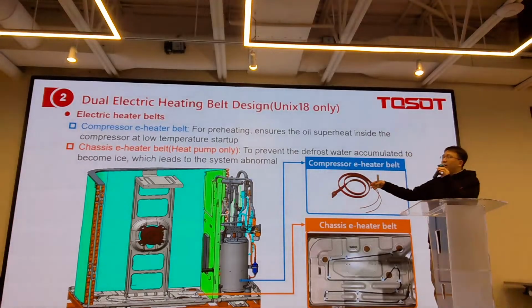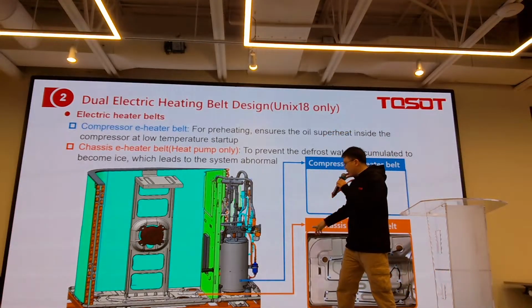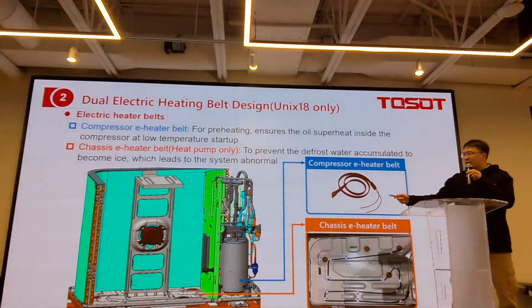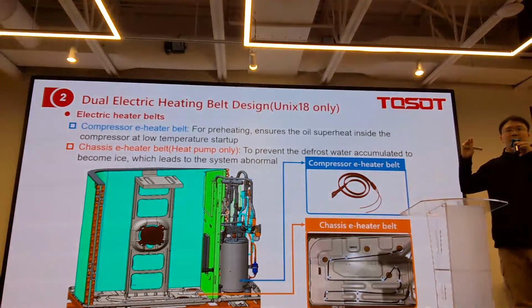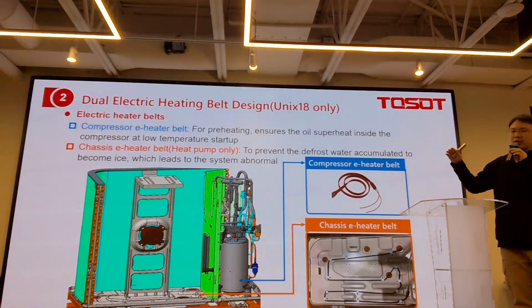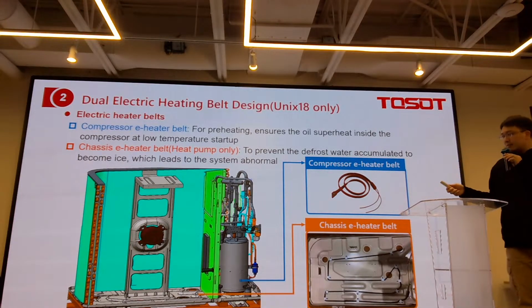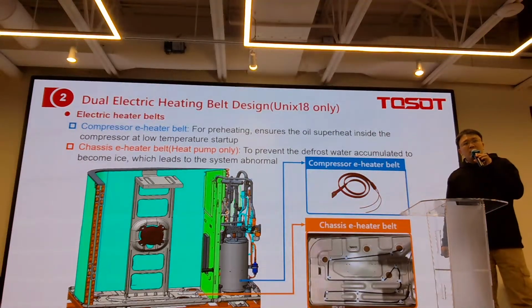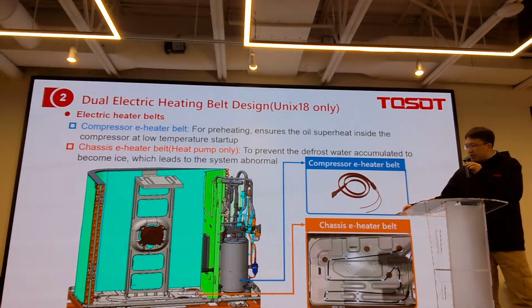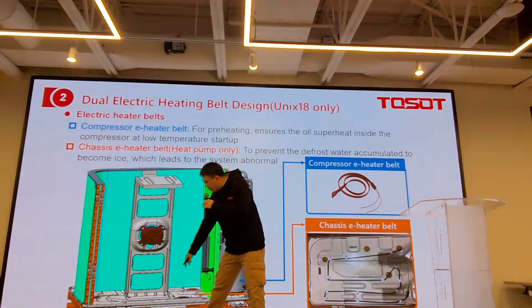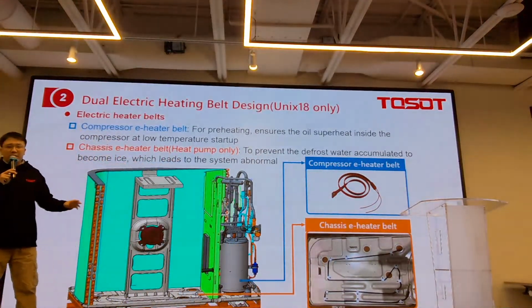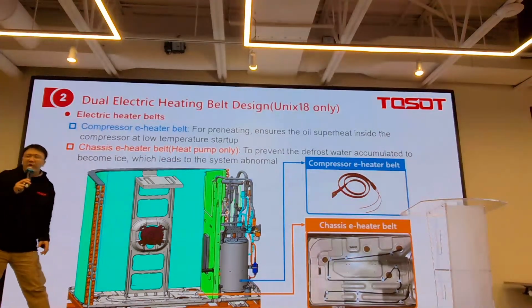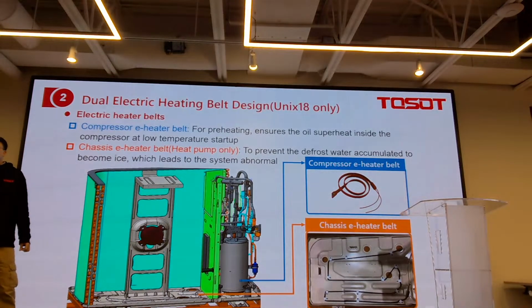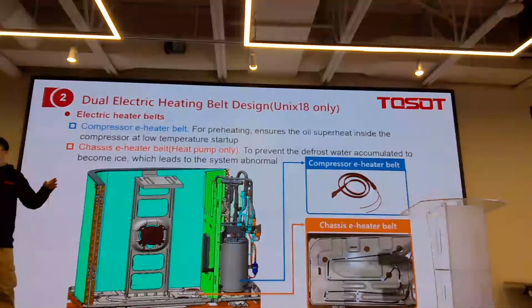And also for the outdoor unit, there are heating belts for the Unix18. One is the compressor heating belt, and the other is at the chassis. The purpose of the chassis one is just to melt, or to guarantee that the water will not accumulate as ice during the defrost. And of course, if the outdoor ambient is extremely low, for example, less than -10, although we can guarantee there's no ice and the water can flow easily from the drain holes in the chassis, the drain hose, if there's no heat strip, can also become frozen, which means the water cannot flow out, not because the chassis is not hot enough, but just due to the drain hose.